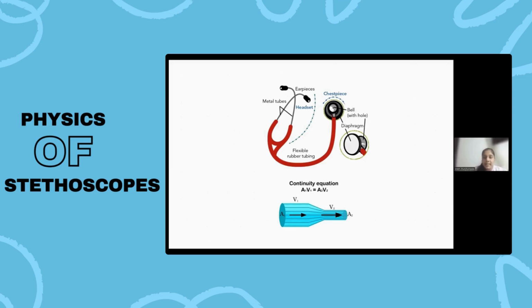So both of these parts capture different frequencies of sounds. The diaphragm captures high frequency sounds such as our regular heartbeats, whereas the bell captures low frequency sounds like murmurs. They transmit the sound waves to the earpiece with the help of the tubing. When sound travels through the tubing, it goes from a larger area of contact, which is the diaphragm, to a smaller area of contact, which is the earpiece. Since the area decreases, the velocity of flow of the air inside the tube increases, and therefore it amplifies the sound waves and gives them more clarity.